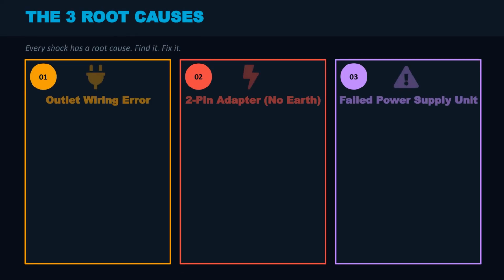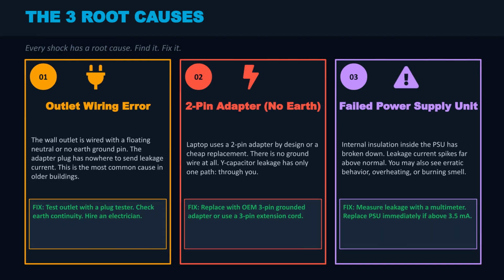There are 3 root causes: faulty outlet wiring, using a 2-pin adapter with no earth ground, or a failed power supply unit. In all cases, the grounding path is broken. You must identify and fix the cause, as current over 3.5 milliamperes can be dangerous.